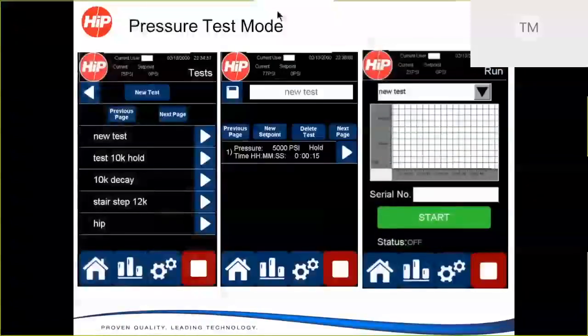So moving on, just a few highlights of the pressure testing screens. We talked about the manual run mode. Now we'll give just a little overview of the automatic pressure mode. If you push the second button from the left, which is the charting function, you'll be in the automated pressure test screen. This is pressure on the y-axis versus time on the x-axis. As you run a test, you'll see your pressure curve increase or decrease accordingly, depending on what you're asking for.